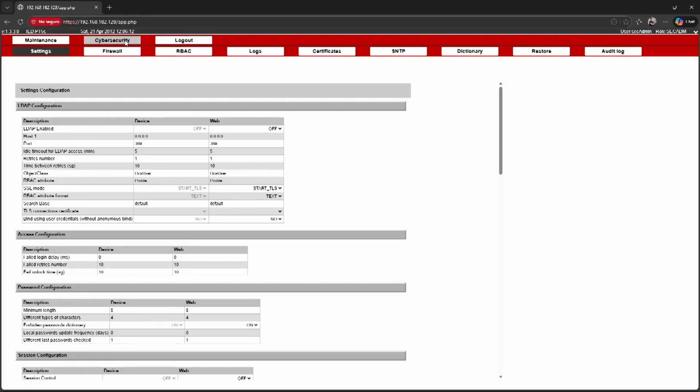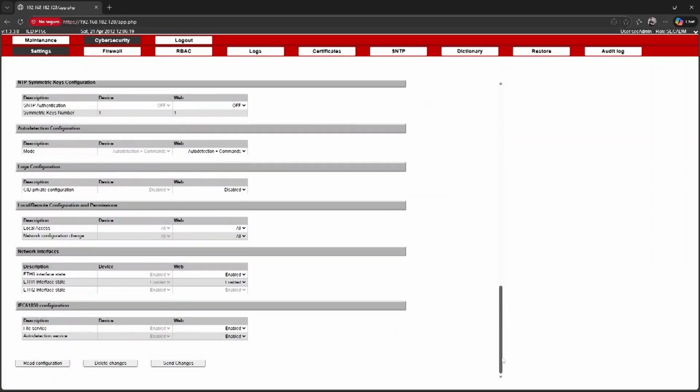Lastly, we will access the web server of our IED, but with the cybersecurity features management credentials instead. We will access the Settings sub-tab inside the Cybersecurity tab and will scroll down, where we will find two blocks of settings. The first section will let us configure whether the network features can be configured locally or remotely, and which connections are considered local or remote. The second section will let us disable all the interfaces, except the one from which we are accessing the IED.